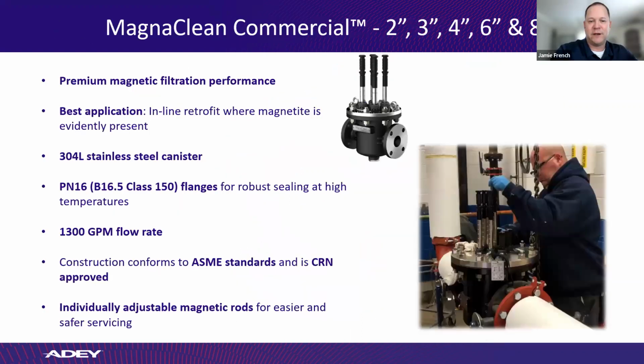And here's the commercial range. Let's jump right into it. MagnaClean commercial, 2 to 8 inch flanged. This is a great product because you get first pass capture. So we're looking at applications where it's a retrofit, where you're designing a new boiler or chiller system into an existing building. You don't know what's in those pipes. You can flush it as much as you can. You're not repiping anything other than near boiler piping. So it's important to have something like this in your spec. And on the right, there is actually Newark Airport in New Jersey, where they were having issues and they put a 6-inch in there. So they're taking care of their problems after the fact.